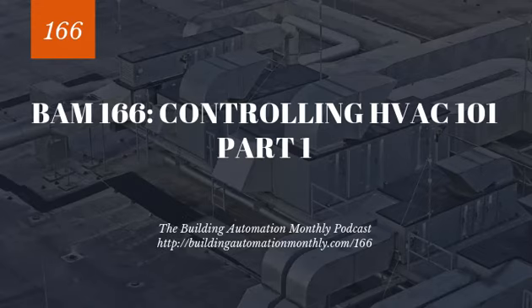Because one of the most important things to realize when you're a controls technician, whether you're on service, whether you're an install job, whether you're in sales, when you're looking at a space, if you have an issue with a space that you're trying to control, then that issue should first focus in on the airflow. Because if you don't have proper airflow in the space, both from a supply and an exhaust perspective, it doesn't matter what you do, you're going to be unable to control all the other variables.